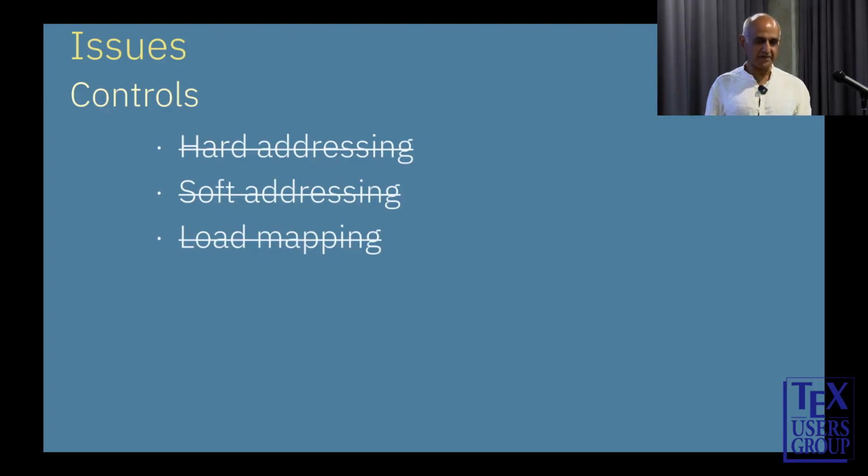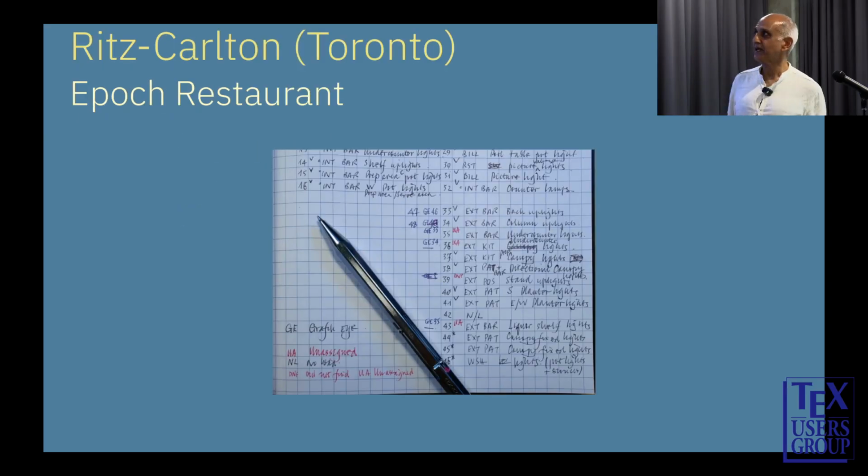So what's to be done? What then must we do? I came and did an audit. And I did the addressing. I mapped all the light loads, the panels, the hard addressing, the soft addressing.